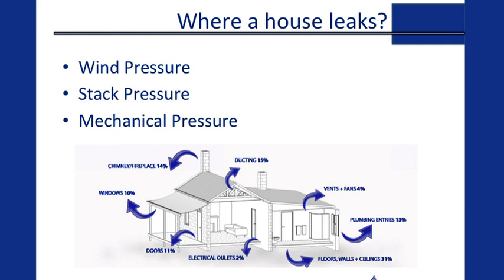So, where does a house leak? There are three types of pressure that affect air leakage: wind pressure, stack pressure, and mechanical pressure. Looking at a typical cross-section of a cottage, most of the leakage is actually coming from the top and the bottom of the building. Those are the primary areas, both for new and existing housing, that you want to start sealing up — in particular, to control the effects of stack pressure.